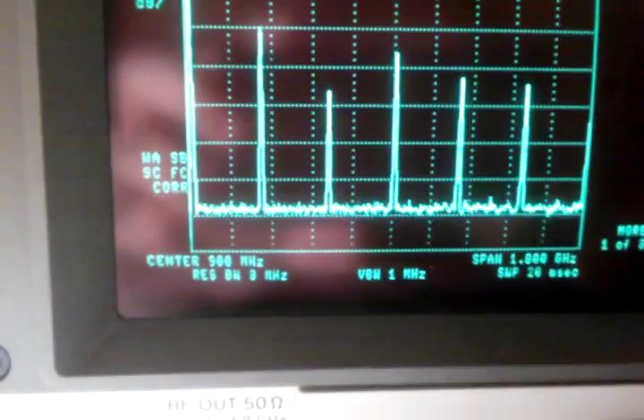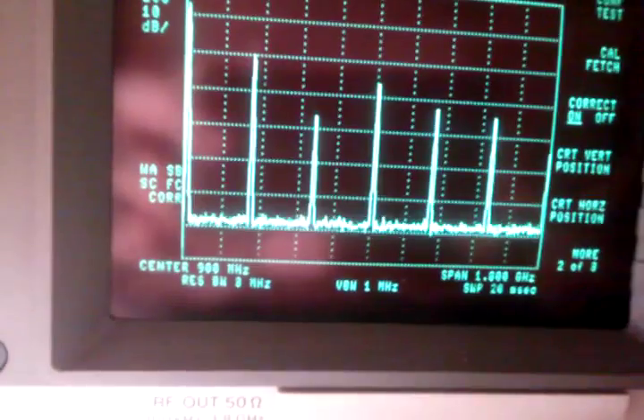Now you can tell on a few of them, what you want to look at is where it says BW amp. That's bandwidth amp, amplitude. A few of them are a little high, the 1.66, the 1.39, the 1.29. They really should be about 0.89 or 0.85 at maximum, but it did not fail and it's well within spec. So, you know, I'm just not going to mess with it. It works. So what we're going to do now is preset and do one more confidence test.